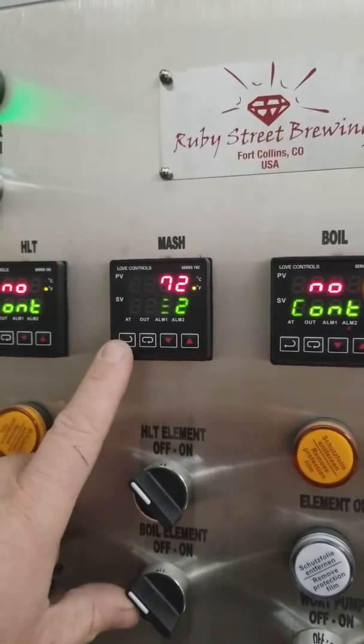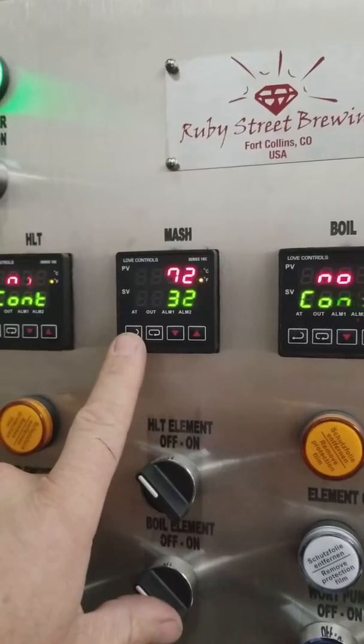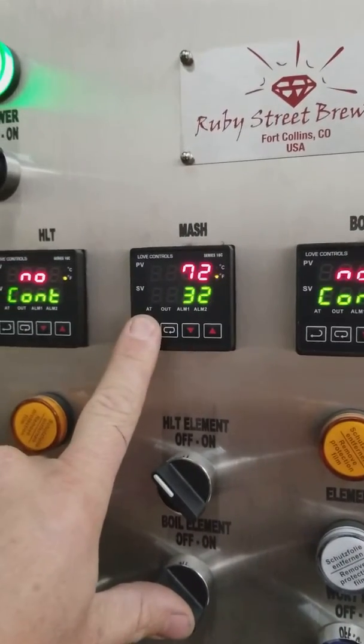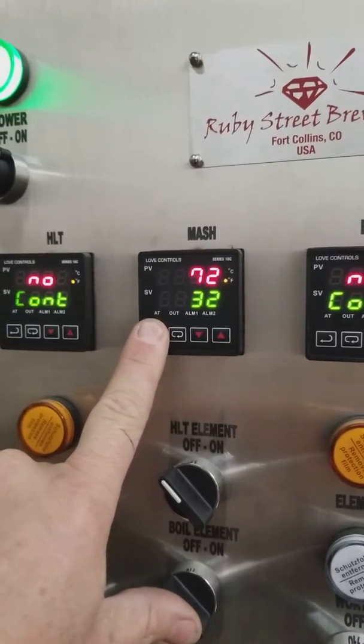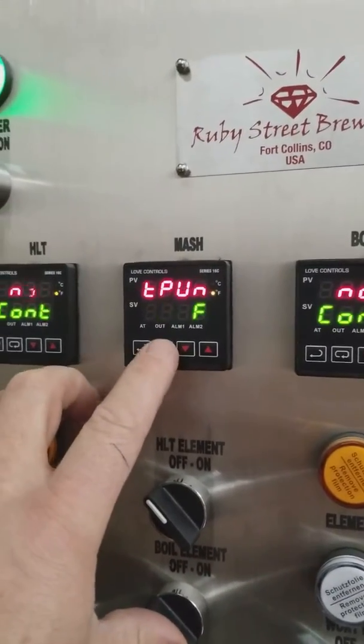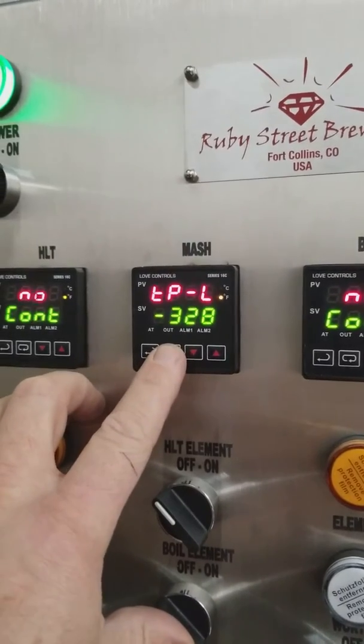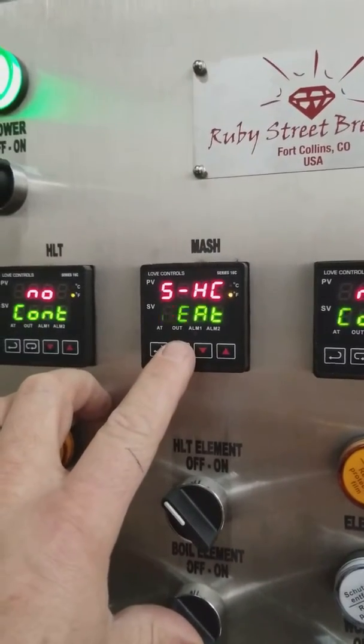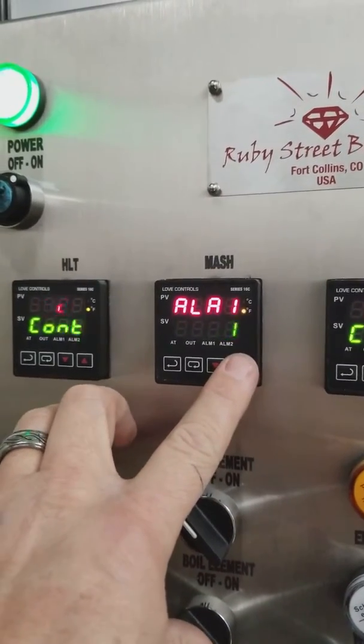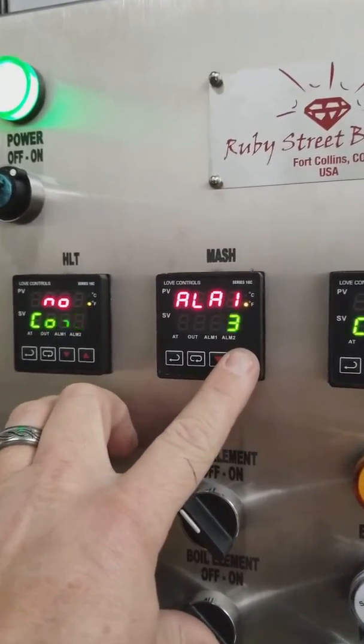The first thing we're going to do is use the set key and the index key. We'll press and hold the set key until it enters configuration mode. Once we're in configuration mode, we can scroll through our settings with the index key, and we're going to scroll through until we see alarm 1. At alarm 1, we're going to change the configuration to 3.